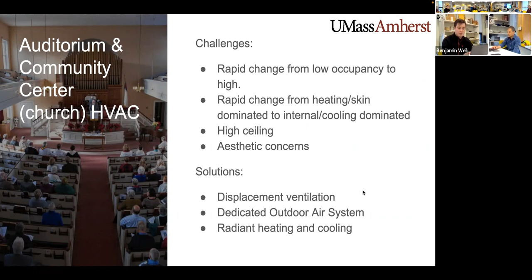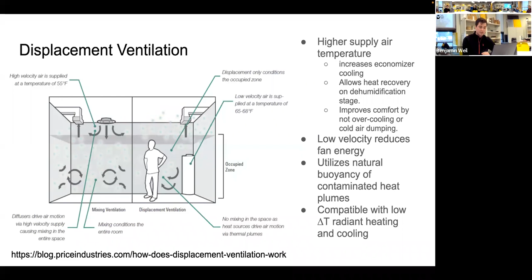Displacement ventilation has a higher supply air temperature, which allows economizer cooling to increase. It allows heat recovery and improves occupant comfort by not overcooling. Displacement ventilation has low velocity, which reduces fan energy. It utilizes natural buoyancy of contaminated heat plumes, which will be shown in the next few slides. It is also compatible with low temperature change, radiant heating and cooling. Heat naturally rises, and with displacement ventilation in place, you have something at ceiling level to take it away.